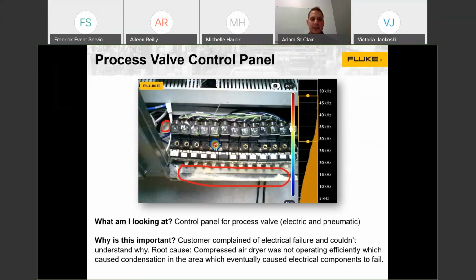This first example is a process valve control panel. The customer came to us saying, we have this issue on this panel, the electrical system keeps shorting out, and we can't figure out why. It's an electric and pneumatic control system, and they thought it was wired wrong or some electrical root cause. So out of curiosity we took an acoustic imager to the control panel and did a quick sound map to see if anything stood out acoustically.